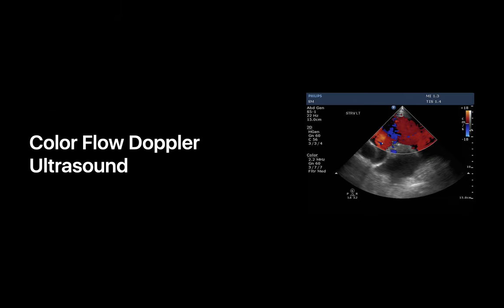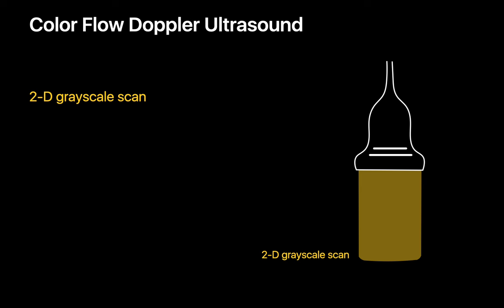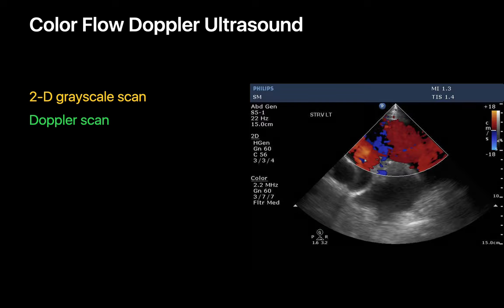Now let's talk about color flow Doppler ultrasound. Color flow Doppler is a nice way to see what the overall blood flow looks like in a large region. It can distinguish flow towards versus away from the transducer, rendering flow direction using a red-blue color spectrum superimposed on the 2D grayscale image. It provides a sense of flow direction, velocity, and whether flow seems turbulent. However, compared to 2D grayscale imaging, the temporal resolution or frame rate of color Doppler is usually noticeably worse, since the transducer must simultaneously create and update both the grayscale and color flow Doppler images.